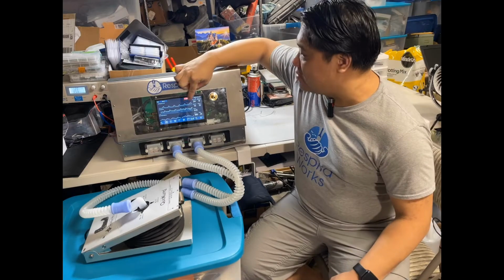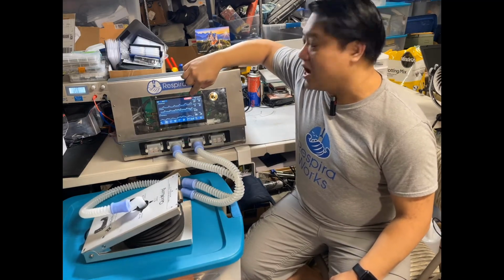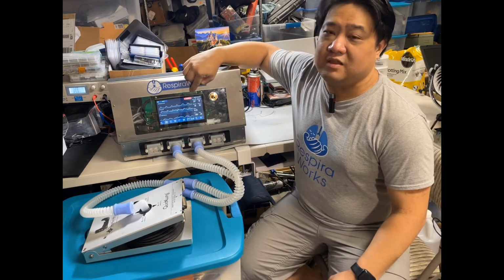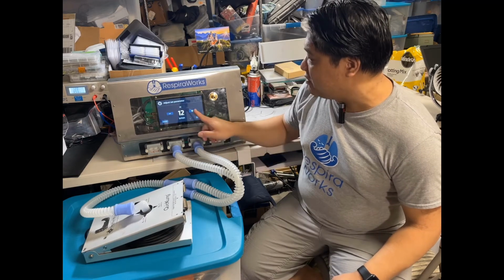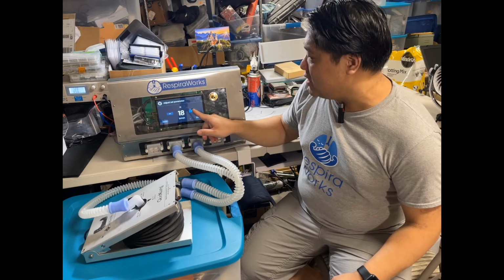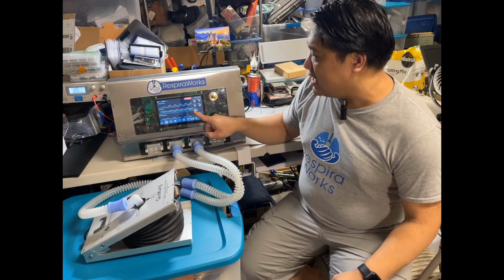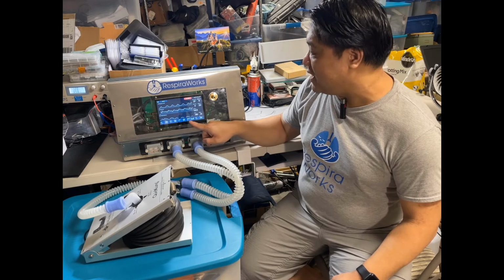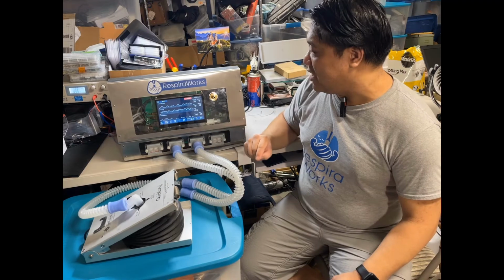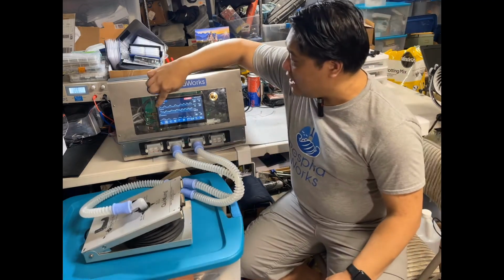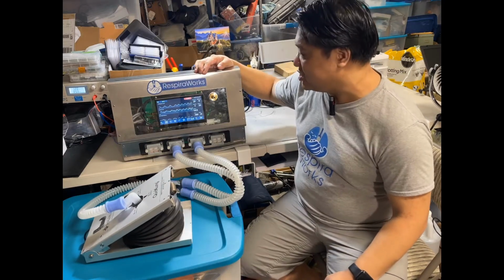And you'll see here that alarms also have a timer. So if an alarm is paused, when this timer runs out, it will reinitiate the visual and auditory alarm. So we're here at respiration rate, and we can set that to 20 breaths per minute. And you'll also see here on the display that it automatically calculates the IE ratio. So when you set the inspiratory time and the respiratory rate, you get the IE ratio here. And you get a live readout of the pressure, flow, and tidal volume that's being delivered to the patient.